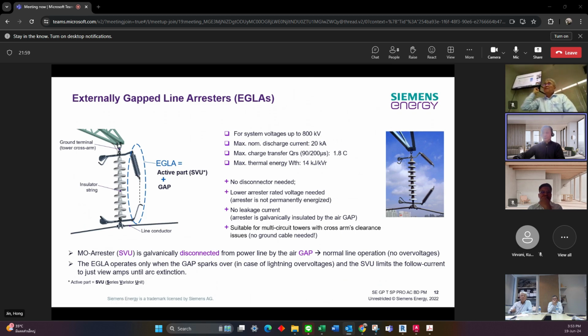The benefit of this design is, how to say, we have no disconnector because we have an air gap. Therefore, even if the surge arrestor itself fails under overloading, no short circuit current can happen here because of the air gap. And we now do not have permanent or constant voltage applied on the surge arrestor itself. Therefore, the configuration of the surge arrestor can use less material and has less manufacturing cost. In comparison to the NGLA, the EGLA type is much cheaper, and also the weight of the EGLA is lighter, which means for the cross arm, we have less weight loading. Yeah? That is also one benefit.